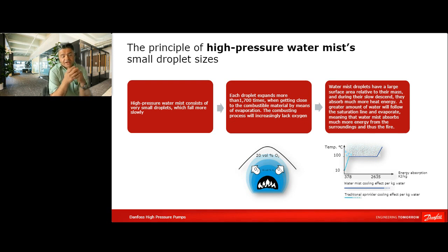And you create a layer of water steam. This layer just lays like a blanket around the fire and you suffocate the fire. What does it mean? The oxygen cannot enter the fire source, so you suffocate the fire. This effect is called oxygen displacement or inertizing. So that's one of the major effects that you have with the high pressure water mist.